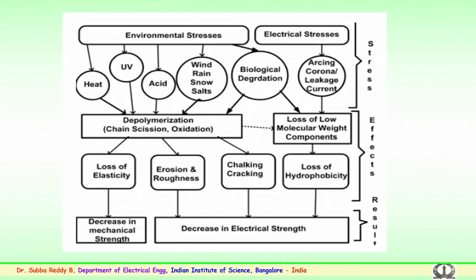Then rain also will aid in the flashover of the insulators. It could cause the surface to become wet. If it is heavy rain, it is a complicating factor where the sheds could be breached. That is the reason the alternate sheds are designed, as mentioned earlier. So, rain could make the surface wet and conducting, and flashover could happen.